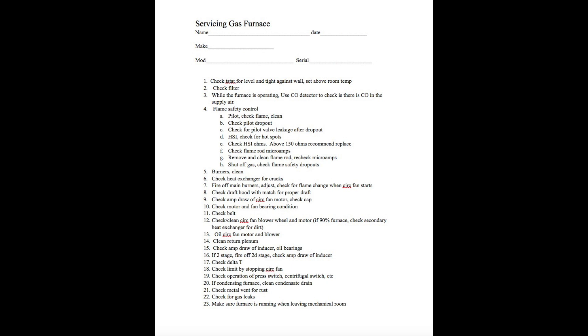While this furnace is operating, you should be using a CO detector in the supply air. Snap it on the supply air, put your CO detector in there, and make sure there's no CO. Because if you get CO, at that point it's no longer a service, it's a repair. You've got to figure out where the CO is coming from. CO, by the way, is carbon monoxide.